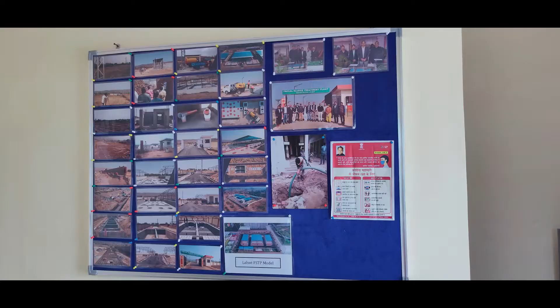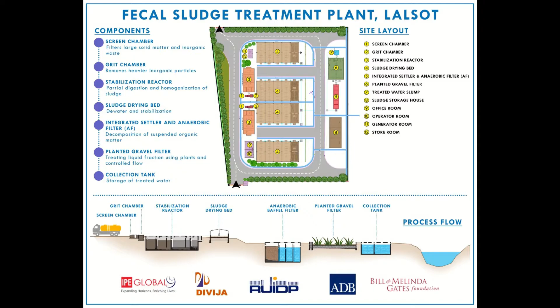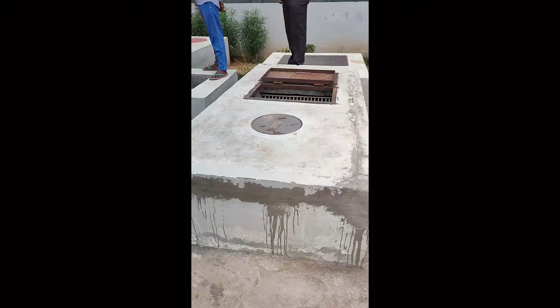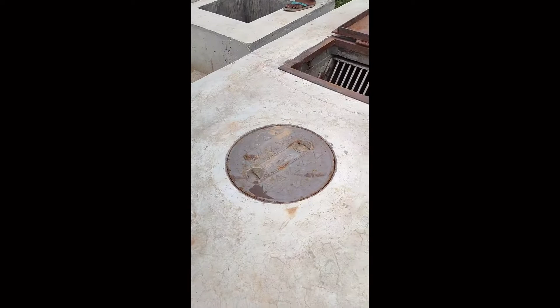The fecal sludge treatment plant in Lalsot is of 20 KLD capacity. The fecal sludge from households in and around Lalsot within approximately 20 km radius would reach the FSTP 6 days a week through 4000 litre tanker. Initially, the fecal sludge is passed through screening chamber for removing the coarse materials like plastic and other large materials present in the fecal sludge.